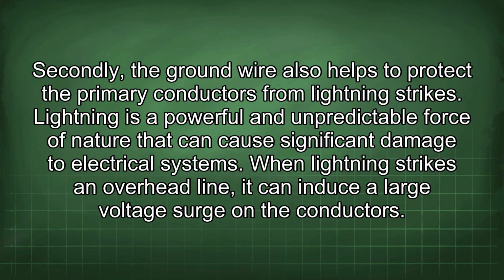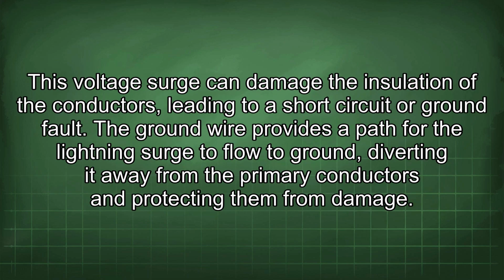Secondly, the ground wire also helps to protect the primary conductors from lightning strikes. Lightning is a powerful and unpredictable force of nature that can cause significant damage to electrical systems. When lightning strikes an overhead line, it can induce a large voltage surge on the conductors. This voltage surge can damage the insulation of the conductors, leading to a short circuit or ground fault. The ground wire provides a path for the lightning surge to flow to ground, diverting it away from the primary conductors and protecting them from damage.